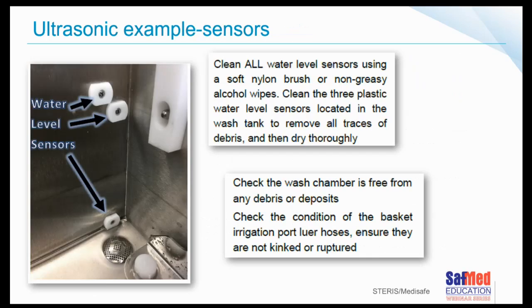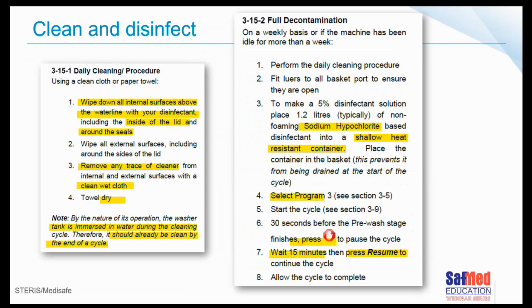Well, how do you do that? You have some of the examples again. The manual should tell you which ones, with images, of course, what is a water sensor, and how do you actually test it. Also very important, on installation, you follow all the installation guidelines, which will include putting your ultrasonic cleaner on a flat surface. If it's not on a flat surface, it could be a problem for these sensors, and if it's incorrect, you could overflow or you could have aborts continuously. Making sure that everything is fine, not kinked, the port hoses are fine, everything as per the instructions.